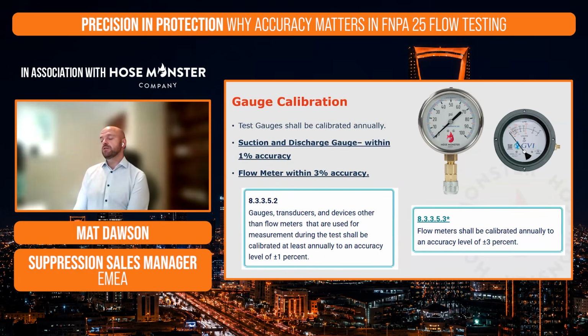So gauge calibration, again, this is something that we see not always followed. So we talk about the accuracy we need to comply with. As per code, we need to have gauges calibrated every year, so annually. There's a couple of tolerances to be aware of. So for fire pump suction and discharge gauges, we need to be within 1% accuracy, and any flow meters need to be within 3% accuracy.